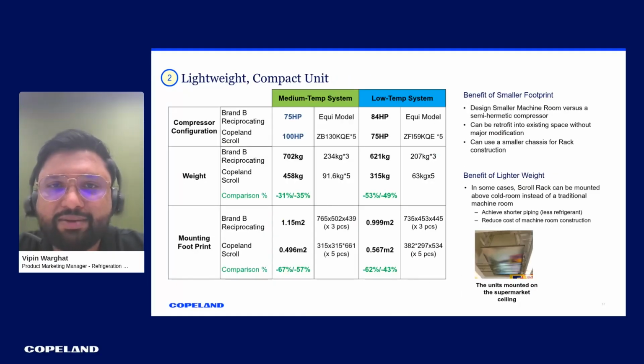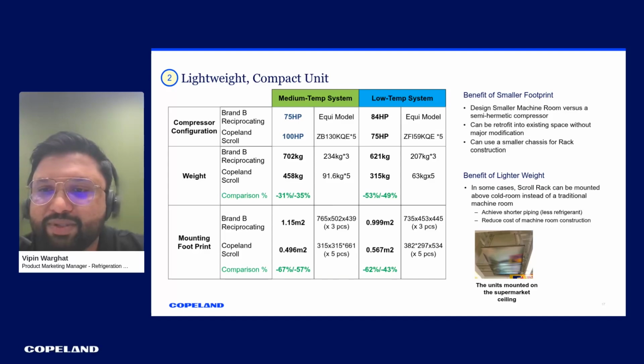Right. And like I was saying, because of the lower footprint and the light weight of the scroll, they were able to get more savings on the system level as well as in space. The medium temp scroll was around 30 to 35% lighter in weight, and 50 to 60% savings were achieved with scroll in terms of space. On the right hand side, they were able to install the scroll rack system on the ceiling itself, as you see in the small picture at the bottom right. This is helping this food retailer a lot, because space is a big constraint for food retail establishments. Okay, if we move on to the next one.